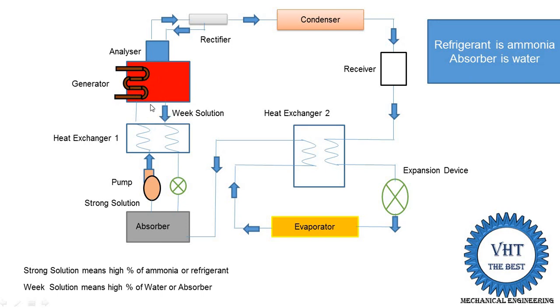The weak solution remaining in the generator — which is the absorber (water) — is supplied back into the absorber. However, the temperature of the weak solution in the generator is high. So we place heat exchanger 1 here: this heat exchanger increases the temperature of the strong solution being supplied into the generator. The weak solution rejects its heat, which is absorbed by the strong solution coming from the absorber, since its temperature is lower. This heat transfer from weak solution to strong solution means the generator receives a pre-heated strong solution.